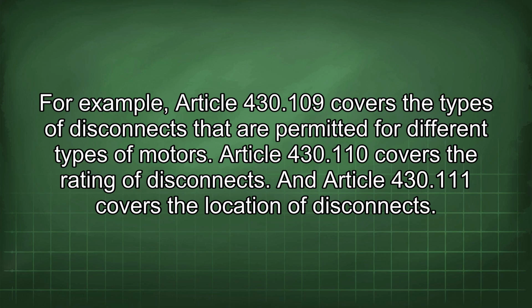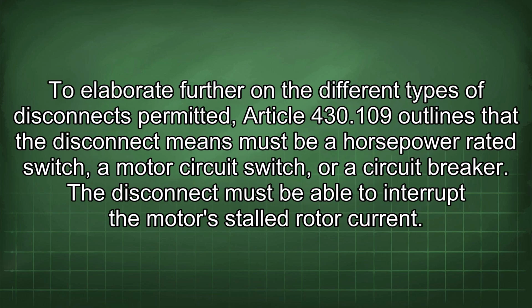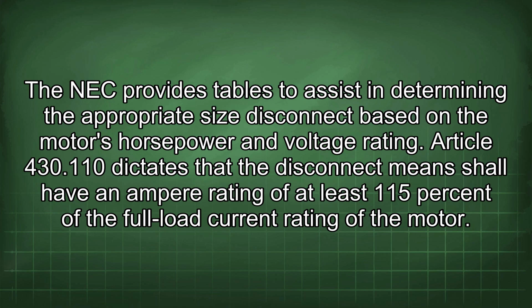Article 430.110 covers the rating of disconnects, and Article 430.111 covers the location of disconnects. To elaborate further on the different types of disconnects permitted, Article 430.109 outlines that the disconnect means must be a horsepower-rated switch, a motor circuit switch, or a circuit breaker. The disconnect must be able to interrupt the motor's stalled rotor current. The NEC provides tables to assist in determining the appropriate size disconnect based on the motor's horsepower and voltage rating.